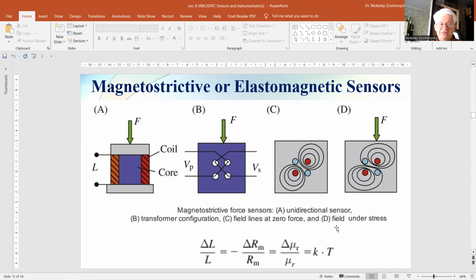Multi-directional devices use the effect that magnetic flux lines change direction when a force is applied. Such a sensor can be used for the measurement of force or torque, and using special designs, for both force and torque simultaneously. Figure B shows a magnetoelastic force sensor configured as a transformer. The core consists of a pile of ferromagnetic lamellae. Both primary and secondary coils have only a few turns, positioned perpendicularly to each other. When no load is applied, the magnetic field lines align with the primary coil, as you can see in figure C, and do not cross the secondary coil, and hence the transfer is lost.